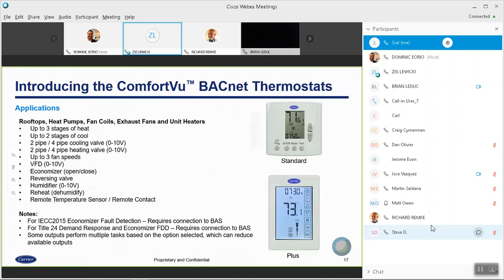You require the IECC 2015 economizer type of fault detection. You will have to use a BAS. So basically, all the messages, all the warnings will have to get pushed to i-Vu, for example, or the other type of BMS applications or UIs. For Title 24, again, you have to marry that with an i-Vu and have OpenADR running with i-Vu.